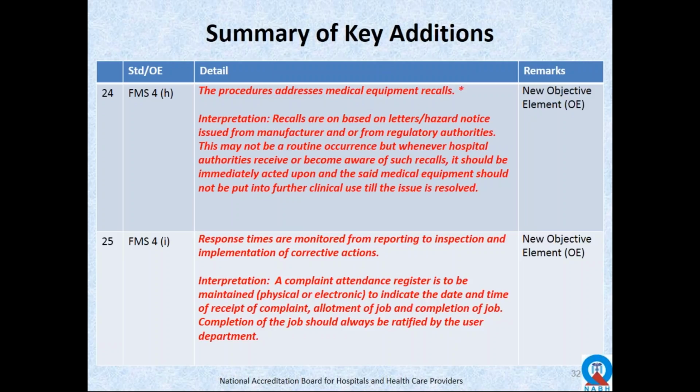And always the completion of job should be ratified by the user department. This is another deficiency which we find often, that it is the biomedical engineering department itself which says that we have now ratified the complaint. The completion of the complaint should always be ratified by the user departments till their satisfaction.